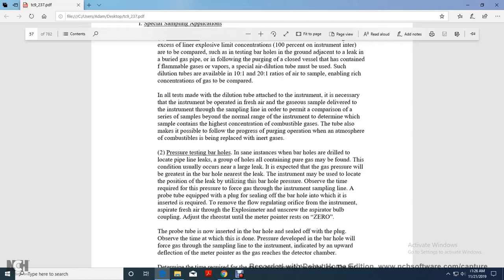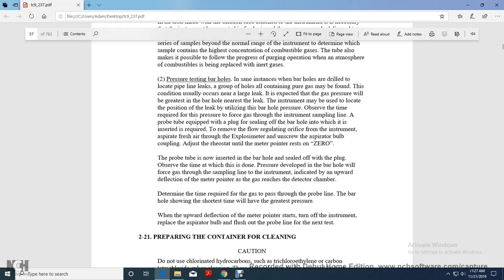Which the sample contained the highest concentration of combustible gas of the tube. It makes it also possible to follow the gaseous progress of the purging operation where the atmosphere of the combustibles is being replaced with inert gas. Alright, 2, pressure testing bar holes.